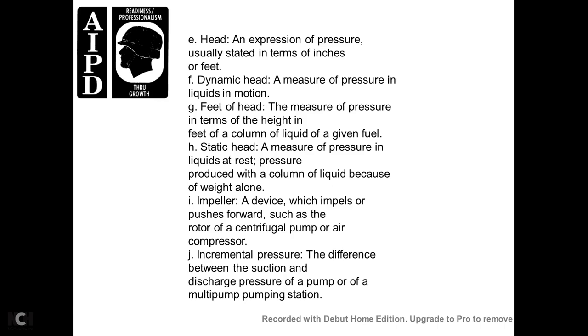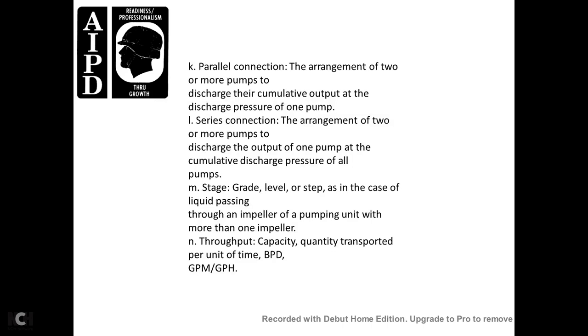Static head is the measure of pressure of liquid at rest — the pressure produced by a column of liquid because of its weight alone. An impeller is a device which impels or pushes forward, such as the rotor of a centrifugal pump or an air compressor. Incremental pressure is the difference between the suction and discharge pressure of a pump. In multiple pump stations using parallel connection, two or more pumps discharge into a common outlet, combining their output at a single discharge pressure.